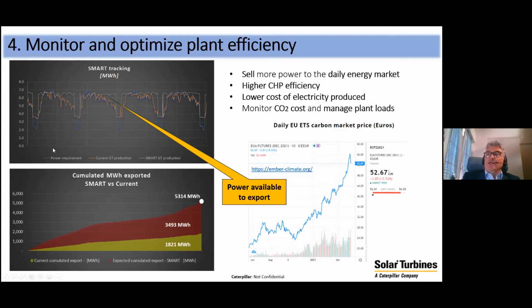In the chart, you can see in the upper chart the system suggesting, in light gray, I would say white line, a different operating condition of the turbine in terms of production of electrical power compared to the requirement of the facility, the blue line, and compared to how the turbine in orange is following the load in electrical load tracking of the facility. In this way, we have the possibility to increase the electrical power produced by the turbine, to participate in external markets, so the daily market, and later on you will see also the demand response market, increasing the amount of electricity that can be sold to the grid.